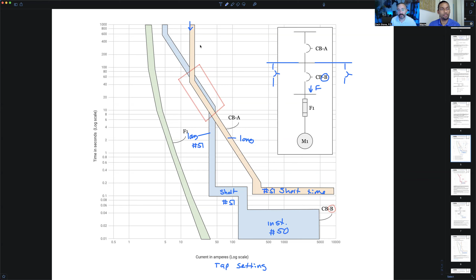Does that make sense? Yes. So if I were to change this tap setting for the long time region for circuit breaker A, this is what it looks like when you draw or adjust these on SKM or EasyPower. I'm just tracing that rectangular portion. So if I can adjust the tap setting, I want to get it away from circuit breaker B and blue. Does this represent an increase or a decrease in the tap setting? That's an increase. That's an increase.